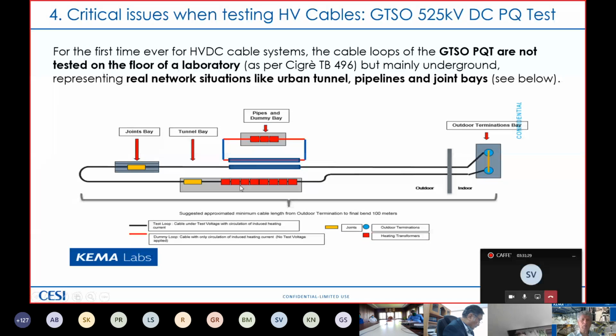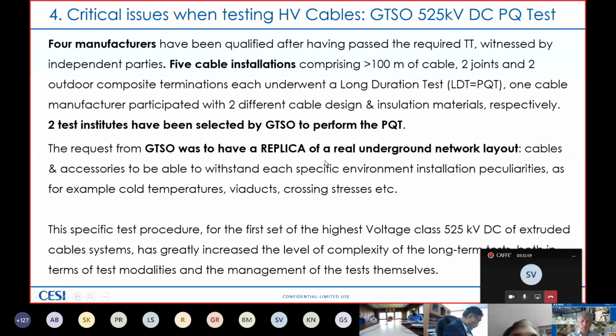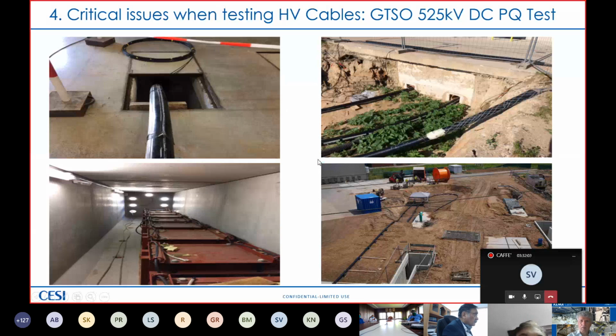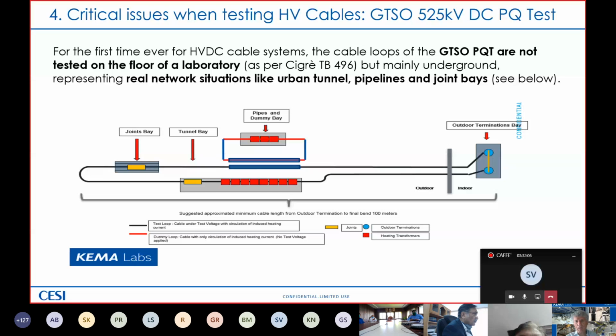Here we have the heating transformers and a cable joint. Then we have a bend that of course is mandatory in the loop. Then we have another joint bay with another kind of joint, one straight, one not straight. Then again, we have a dummy bay area and the pipelines. Both the dummy cable and the real cable enter the pipelines. Then we go back to the underground station and we enter the outdoor termination bay. Even if the terminations are outdoor, the test has been performed indoor.